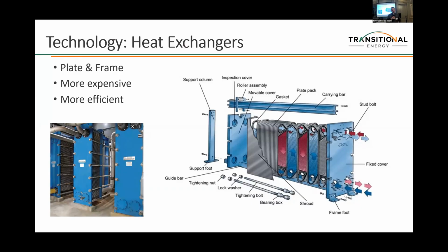There are two different kinds of heat exchangers. There's this one, a plate and frame, which is what it sounds like and what it looks like. The number of plates can vary depending on how much surface area you need to heat exchange with. The gaskets between the plates vary based on your fluid type. If you're heat exchanging with oil, you use different gaskets than if you deal with water, or if you have H2S, you might have a different gasket again.